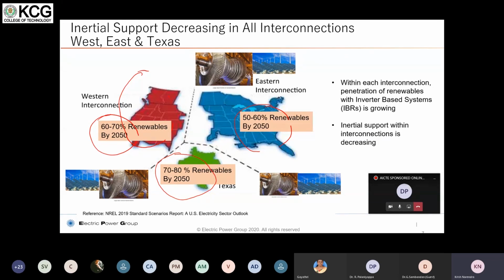So therefore, what happens is, within each region, there's a drastic decrease, and the rate of change of frequency will become very high, and then the frequency drop will be much below the nadir point, which is the minimum point where the current protection systems operate.